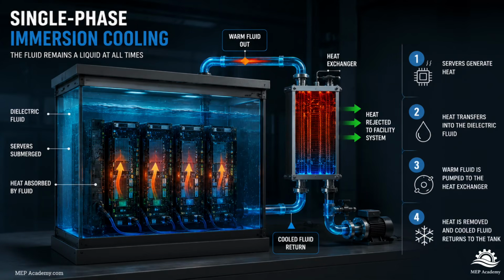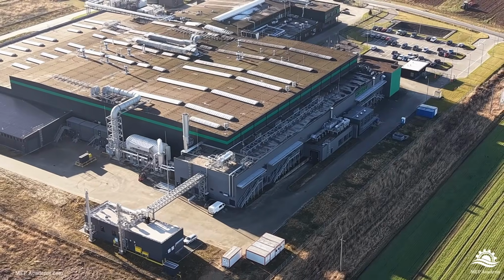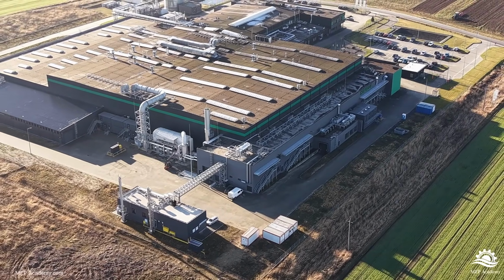There are two primary types of immersion cooling: single-phase immersion cooling and two-phase immersion cooling. Let's start with single-phase. This is currently the most common approach. The dielectric fluid remains a liquid at all times. The fluid absorbs heat from the servers. Pumps circulate the warm fluid to a heat exchanger. Heat is removed. Then the cooled fluid returns back to the tank. Simple, reliable, and relatively straightforward.